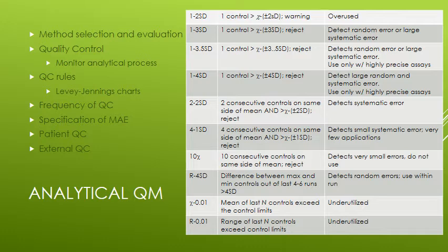You also, at this point, have to be able to compare the accuracy and precision of this new method with any old method that you might be running, if that applies. If this is totally new and it never existed before, that's different. But if this is a new procedure or instrument that's replacing an old one, you have to compare the two and evaluate: is the bias, is the imprecision that we do see, whether it's within run or from day to day, acceptable? Is that something we're okay with?